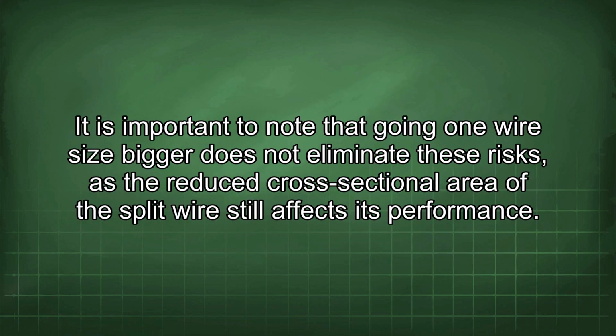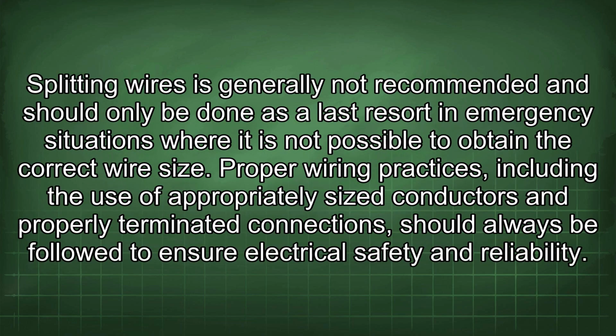It is important to note that going one wire size bigger does not eliminate these risks, as the reduced cross-sectional area of the split wire still affects its performance. Splitting wires is generally not recommended and should only be done as a last resort in emergency situations where it is not possible to obtain the correct wire size.